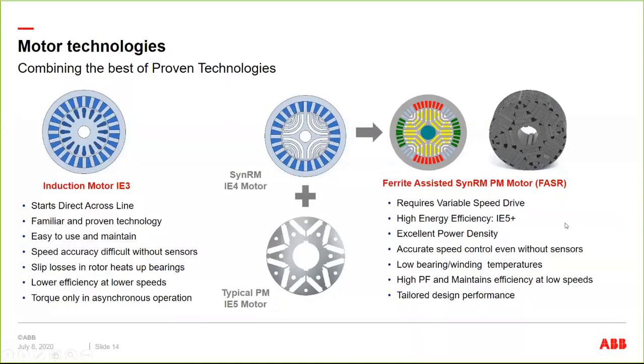Again, we already talked about this: IE5 efficient, excellent power density, accurate speed control. Obviously it's a synchronous motor, so it's going to run at synchronous speed with no slip. So it's always going to give you good speed control. Low bearing and winding temperature and high power factor, and it maintains efficiency at low speeds, which I'll be showing you in a future slide. And tailored design performance, meaning that we have standard stock ratings, but we have pre-configured engineered options. So if you want to do a C-face mount or a pump mount or any type of mechanical mount, that's very easy to do with this product.